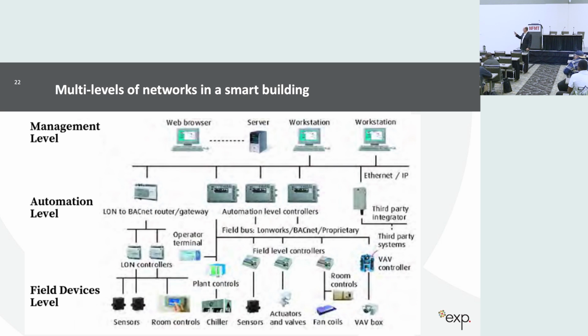Talking about different network levels, remember that diagram with so many levels. This goes into the first three levels. The field level devices are like sensors, VAV boxes, actuators, the end devices. Then you have the automation level, which has more controllers. You can see there's some LON controllers, third-party integration systems, BACnet systems, Modbus systems, all on the control level.